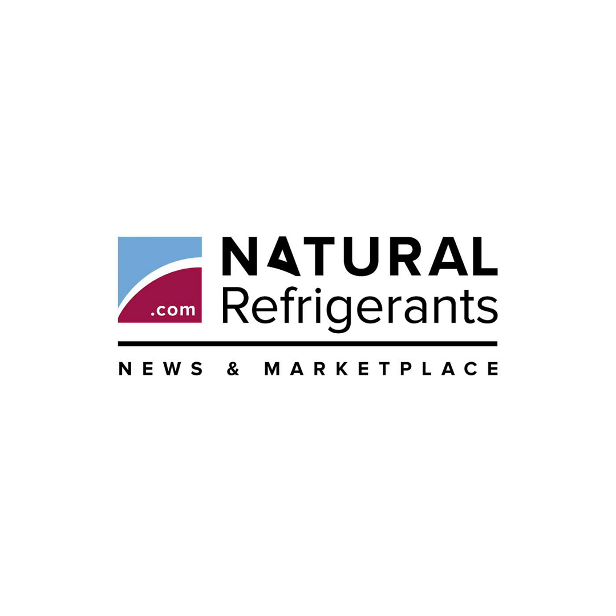At the 2024 FMI Store and Energy Development event, Goldstein reported that the panels improved system efficiency by 15 to 20%, compared to mechanical subcooling, and reduced hours spent in transcritical operation by 50 to 100%, depending on the conditions. Retrofit planning. With the closed thermal loop, Skycool's panels support any refrigeration system, regardless of the refrigerant. When updating a store to CO2 refrigeration, the panels previously installed to support an aging system integrate into the new setup by replacing the heat exchanger.